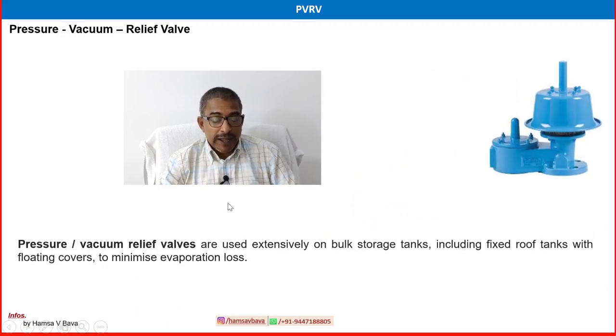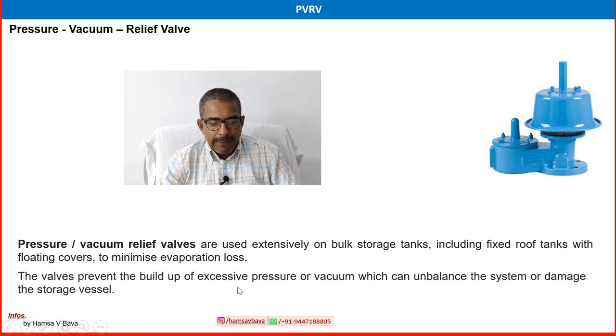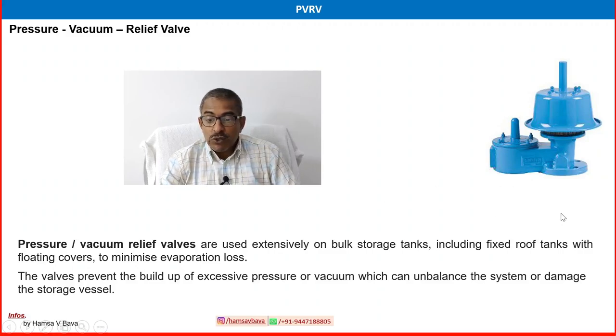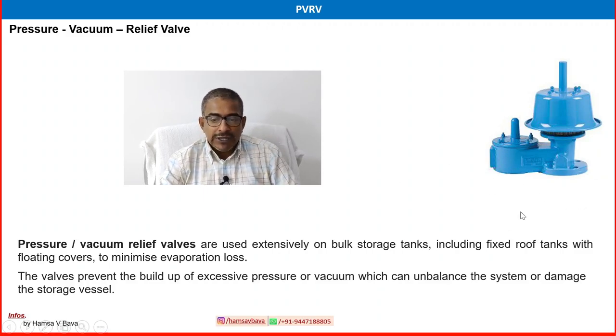One more valve to cover at the end of this video: the pressure vacuum relief valve (PVRV). Pressure vacuum relief valves are used extensively on bulk storage tanks, including fixed roof tanks with floating covers, to minimize evaporation loss. This valve prevents the buildup of excessive pressure or vacuum, which can unbalance the system or damage the process vessel. It works in both directions — releasing excess internal pressure externally, and allowing atmospheric air or gas inside when vacuum conditions develop.